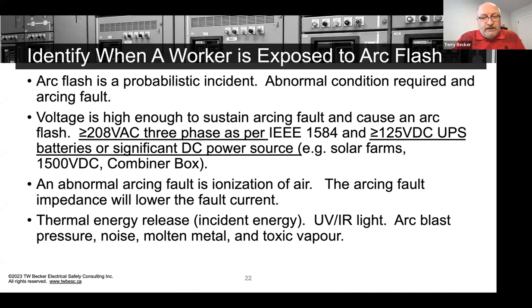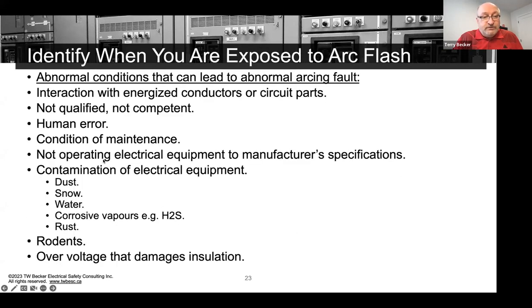And then there's UV light, there's pressure. When we instantaneously get that abnormal arcing fault, it expands air, right? It does vaporize copper, but it's not the copper that's creating the pressure. It's the instantaneous expansion of air. We do get molten metal, of course. And then when we vaporize copper, it creates a toxic vapor, or a smoke, right? So these are other abnormal conditions that can cause an abnormal arcing fault to occur.